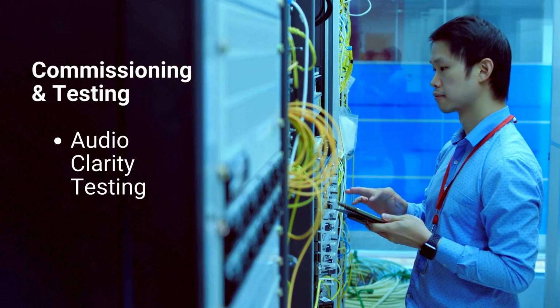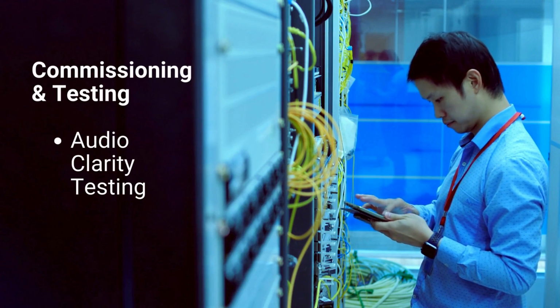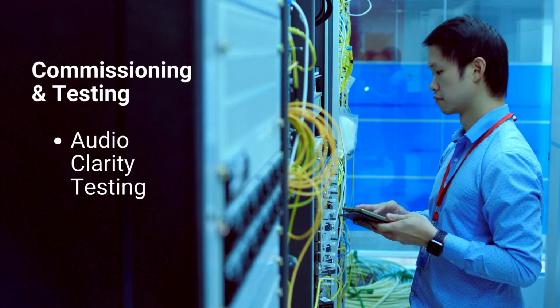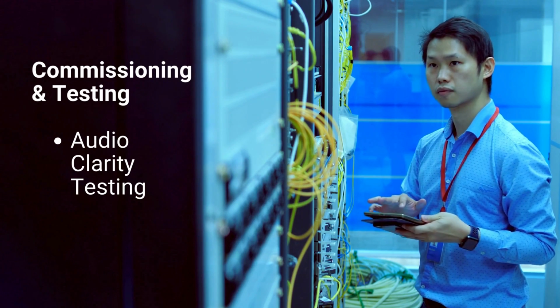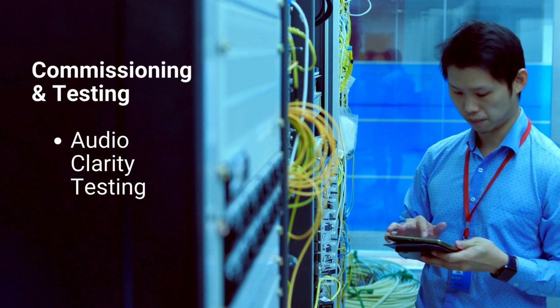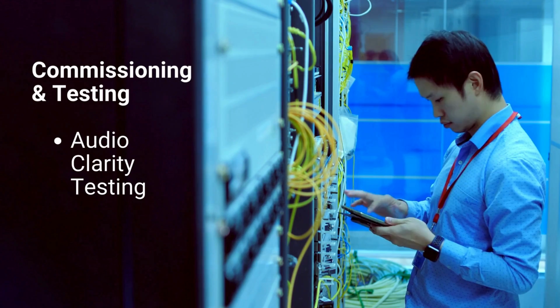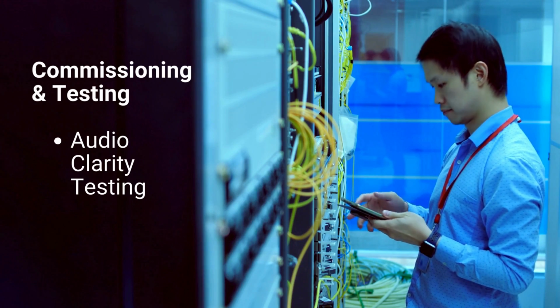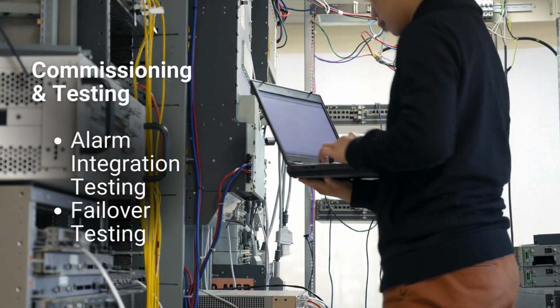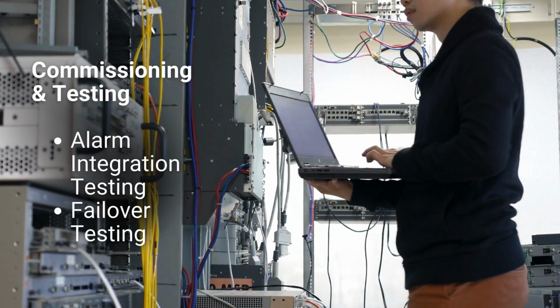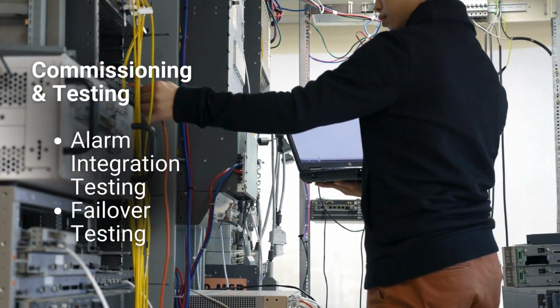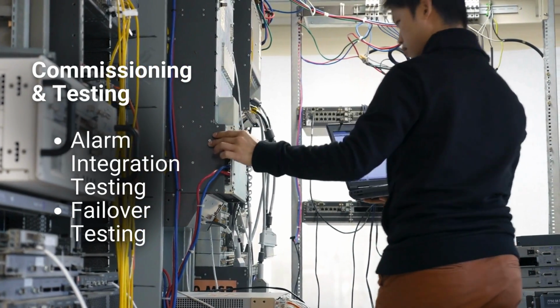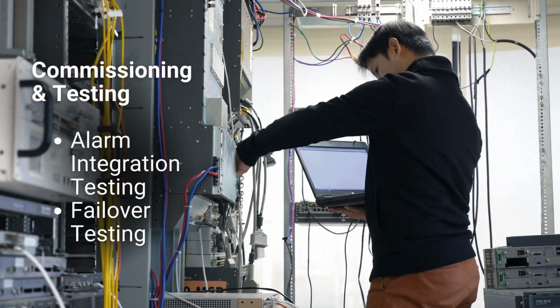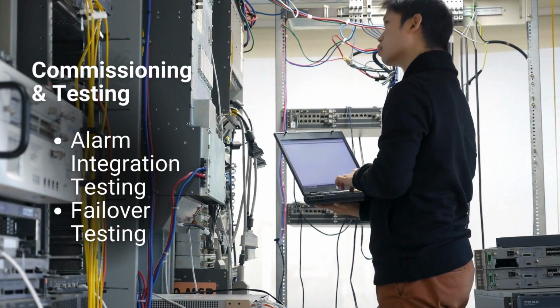Commissioning and testing. Commissioning is the final phase where the system is tested in real-world conditions. Technicians perform a variety of tests, including audio clarity testing, verifying that communication is clear and audible across all stations. Alarm integration testing, ensuring that the system automatically interfaces with alarms and other emergency signals. Failover testing, simulating network failures to test redundancy and system resilience.